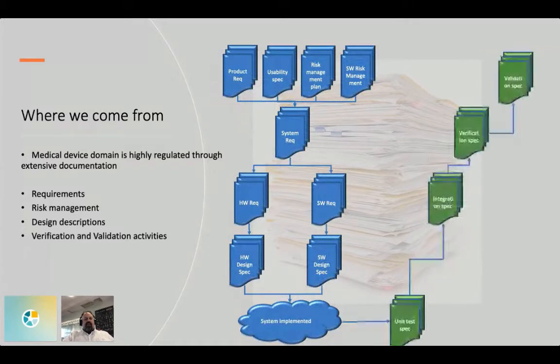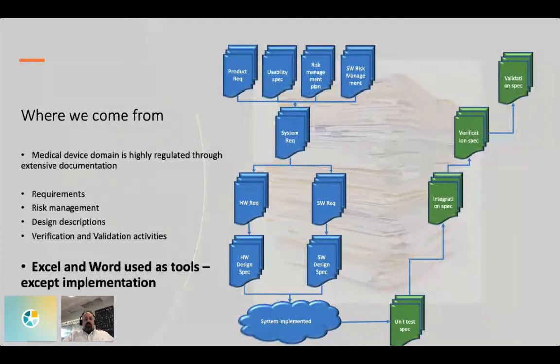These also need to have a test suite connected in the form of unit tests, integration tests, verification specifications, and validation specs. It's a highly document-driven domain. The tools are Excel and Word — and as in most companies we use them extensively. We do connections between them, and if something happens — say a product requirement or usability aspect is changed — it falls down through many of these documents that need to be updated.